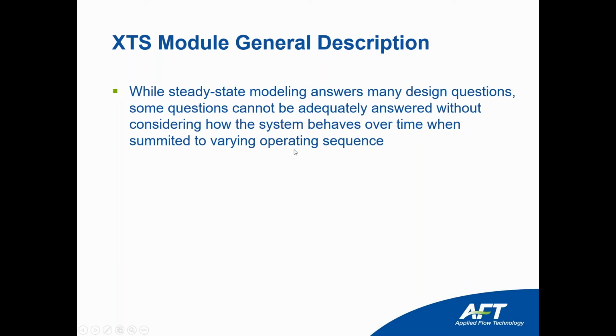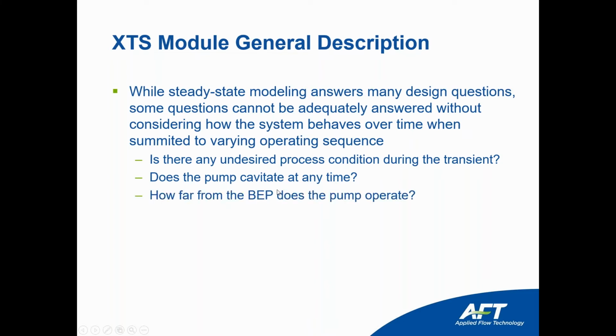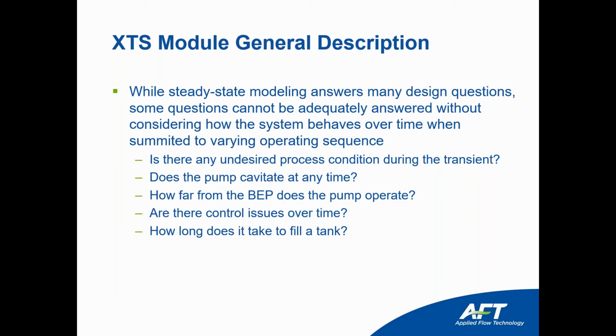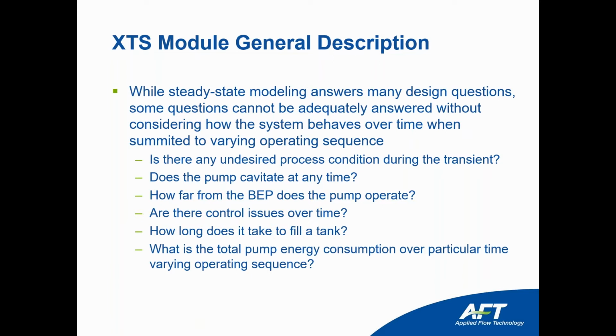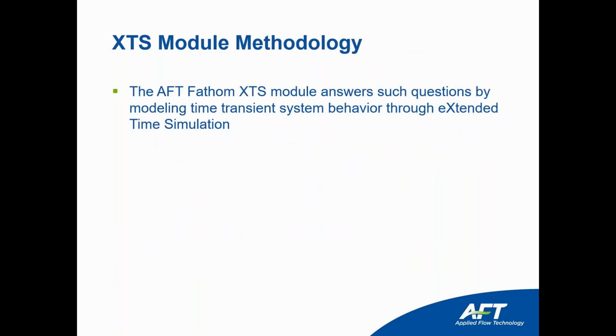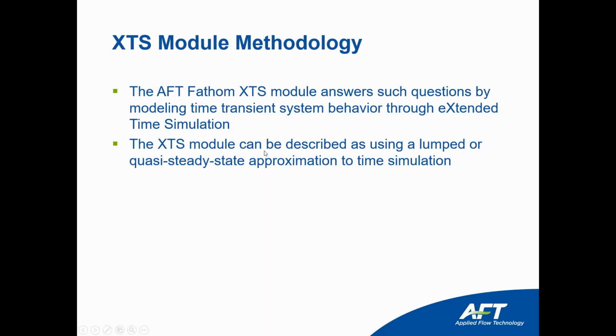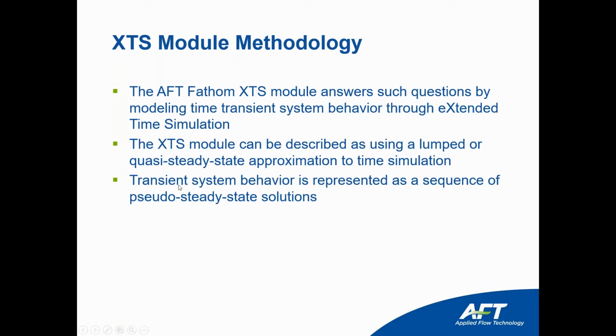So let's start talking about the XTS module. Let's do a brief introduction of the module. Basically, steady state modeling answers many design questions, and that is what AFT Fathom alone is designed for. Some questions cannot be adequately answered without considering how the system behaves over time when subjected to a varying operating sequence. Like, is there any undesired process condition during the transient? Does the pump cavitate at any time? How far from the BEP point does the pump operate? Are there any control issues over time? How long does it take to fill a tank? What is the total pump energy consumption over a particular time, with a varying operating sequence?